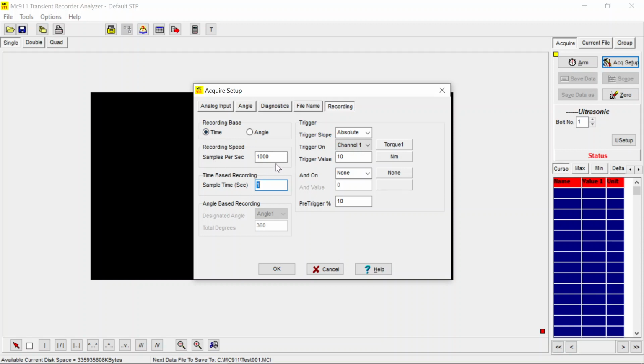Our samples per second is 1,000 samples per second. And let's increase our sample time to 10 seconds. And for the rest, we're going to trigger on channel 1, which is torque, and we start recording at 10 Newton meter. And we have 10% pre-trigger. Okay, we are set for that.